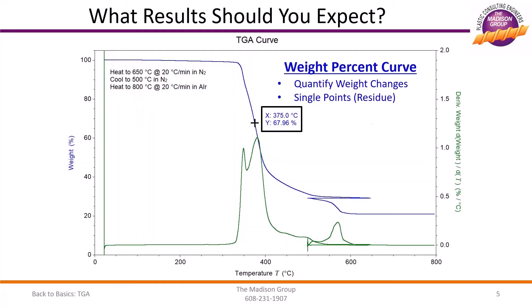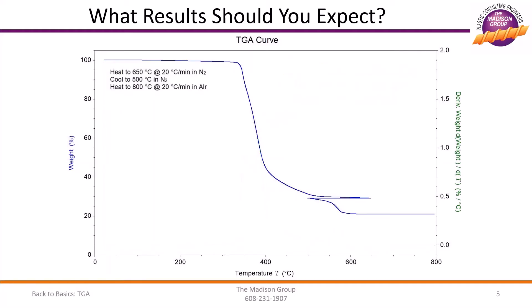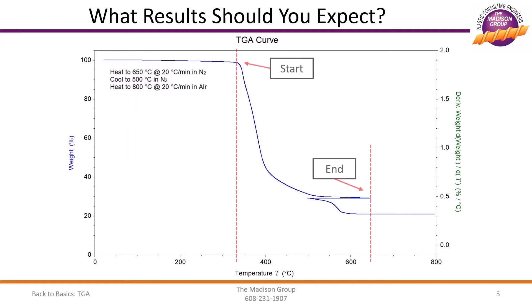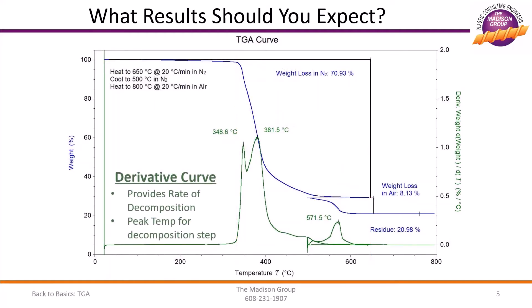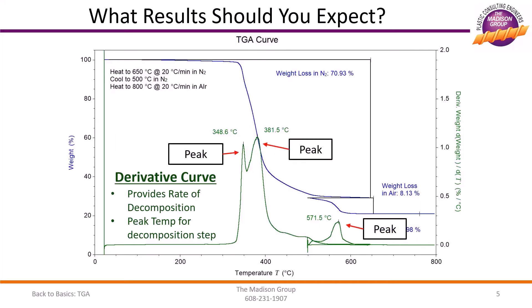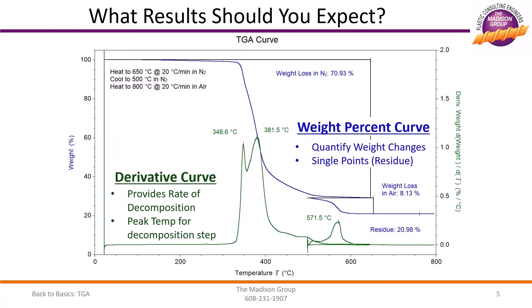The weight percent curve is primarily used to determine the amount of weight changes for each decomposition step in the plastic, as well as the amount of inorganic residue left after completion of testing. The usefulness of the derivative curve can be observed by removing it from the graph. While the approximate temperature range for an individual decomposition step can be eyeballed on the weight percent graph, it is much more difficult to accurately determine the temperature at the center of the decomposition step, or if it is centered around multiple temperatures. The derivative curve clearly shows the temperatures at which each decomposition step starts and ends, and allows you to accurately assess the changing rate of decomposition to determine the temperature of maximum decomposition rate, or whether there are multiple maximums for a single decomposition step. Both curves are used to accurately and precisely assess the TGA data.